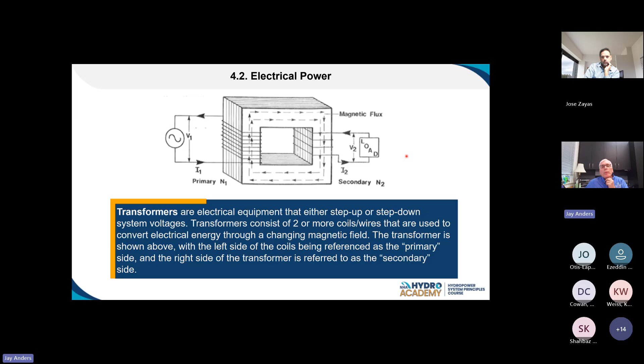So what we do is we connect our generators to the low side, and on the high side, we connect the grid. From that, we step up the voltage that goes out to the grid. We generate at 13,000 volts. We come out of these transformers at maybe 161,000 volts.